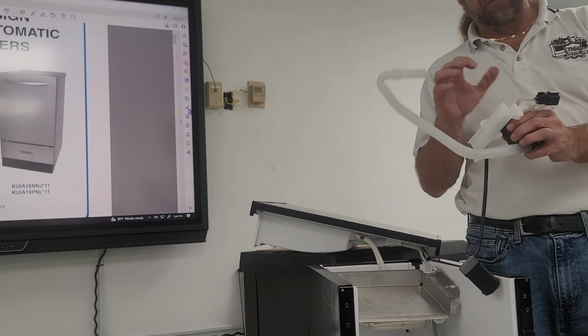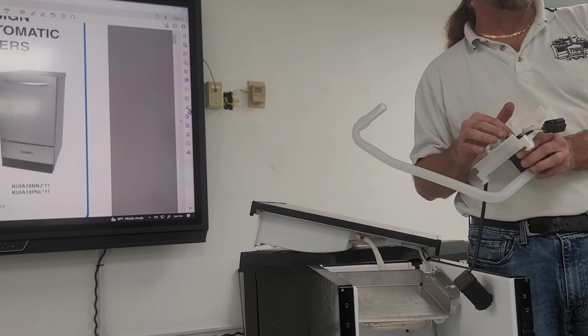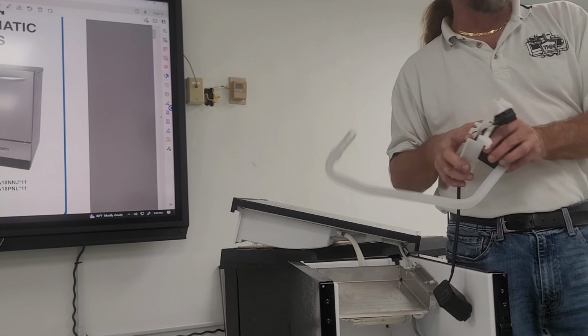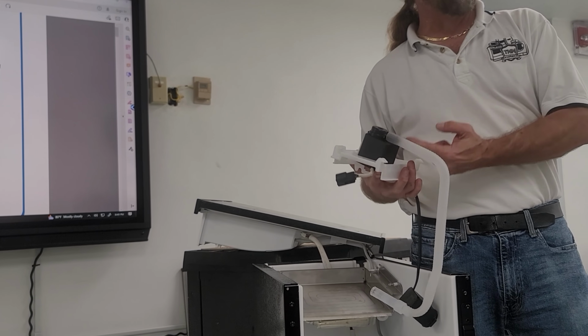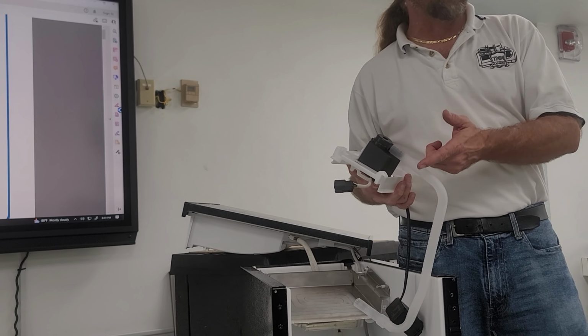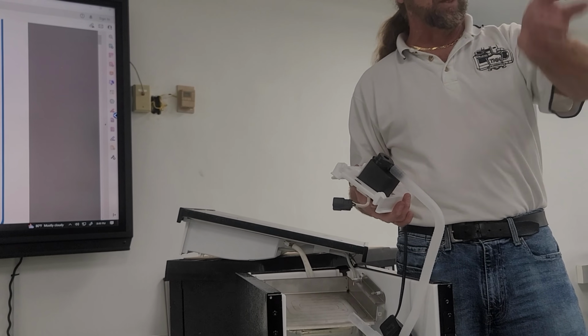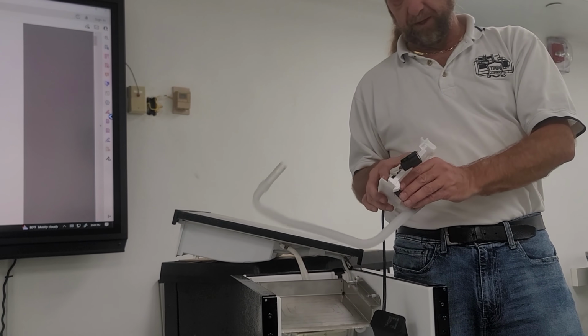And sometimes this pump just builds up with algae. It's not that the pump is always bad. So what you want to do is take this hose off and check to make sure it's clear and there's no obstruction. And if it's still not circulating water, then we have to replace this pump.